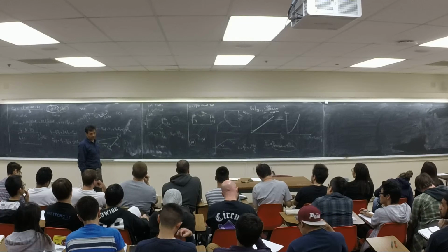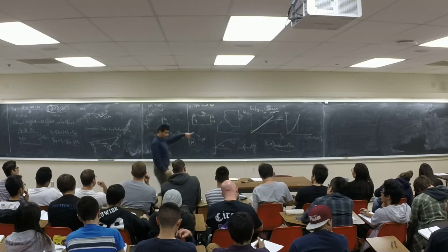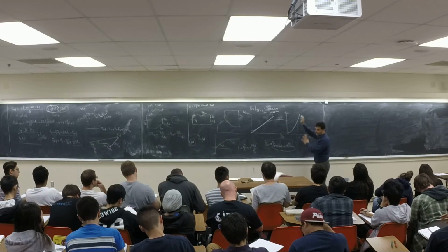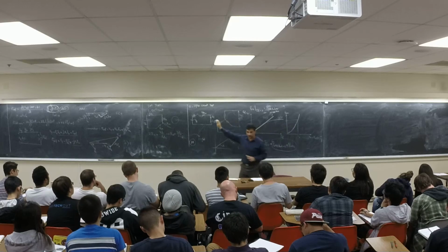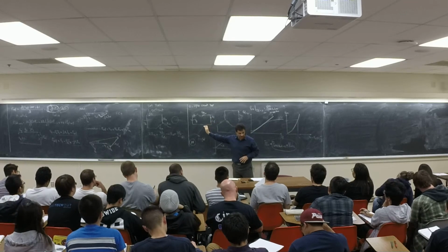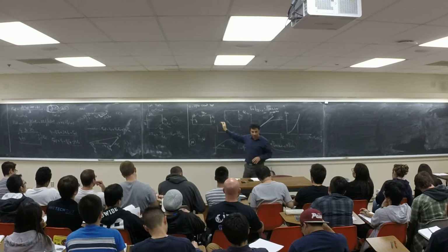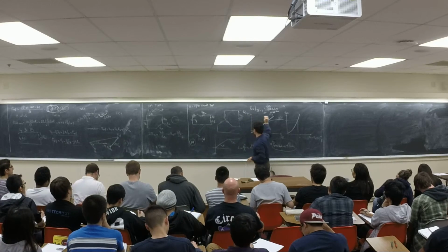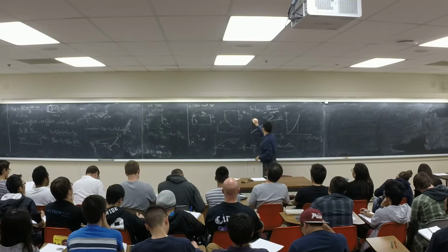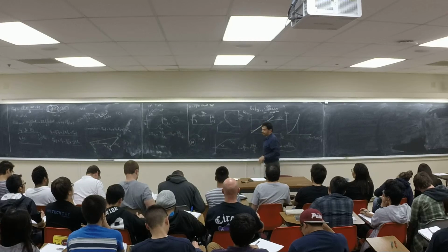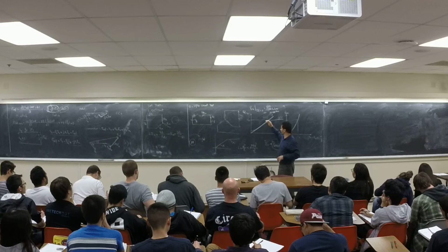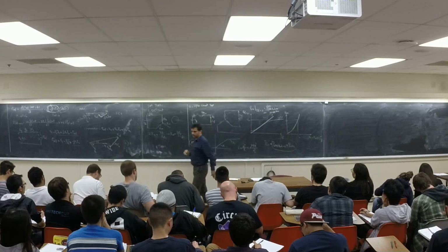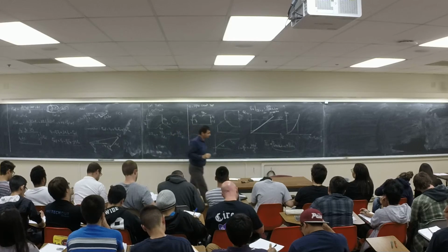The next one is the short circuit test. I'm going to use this one, so keep this one in mind. But let's go to the short circuit. So what was the test condition? The machine is rotating. This is very important. The machine is rotating at synchronous speed, and we are increasing IF from 0 to some value which generates the rated voltage, Vn here, right? We are going to go there. You can go a little bit more if you want, but not more than 5 to 10%. You keep it there. Now we are going to go to the short circuit test.